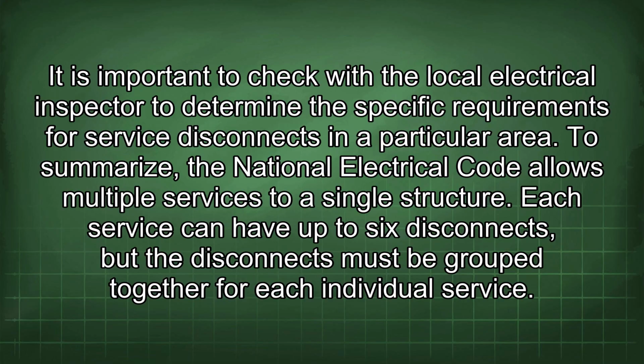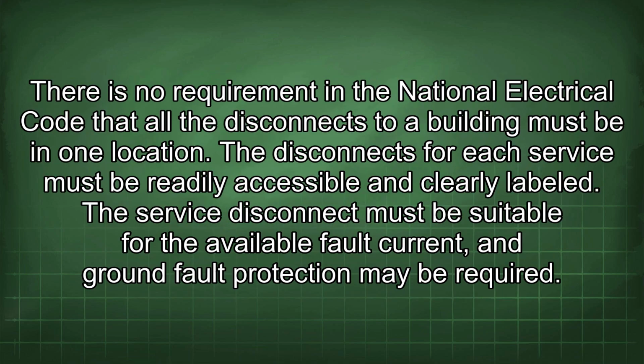To summarize, the National Electrical Code allows multiple services to a single structure. Each service can have up to 6 disconnects, but the disconnects must be grouped together for each individual service. There is no requirement in the National Electrical Code that all the disconnects to a building must be in one location. The disconnects for each service must be readily accessible and clearly labeled.